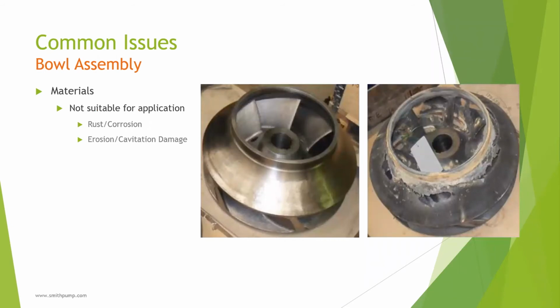Not all pumps are created equal, and the same goes for impeller materials. Always specify a suitable material for the application. Shown are the before and after of a severe erosion on this impeller. The standard impeller material for most vendors is some sort of bronze alloy. The standard bronze alloy is good for most applications, but may not be good for your application. If there will be corrosives in the fluid, an upgrade to stainless steel could be worth it.